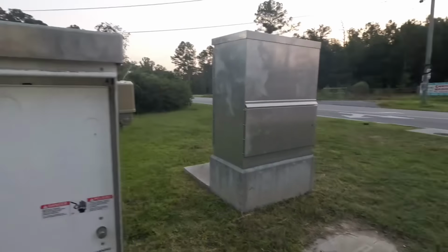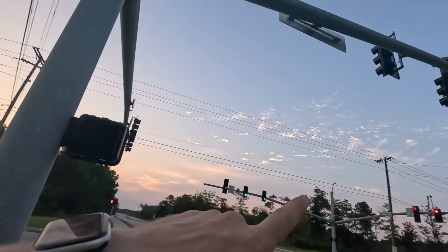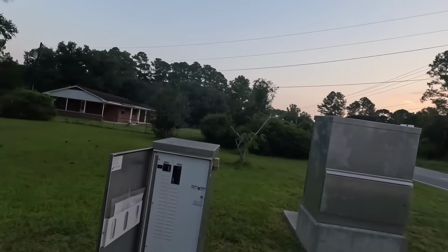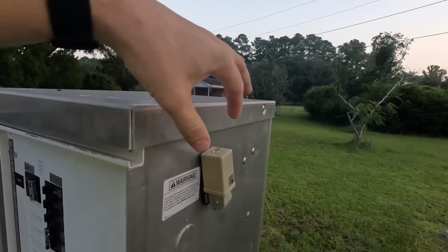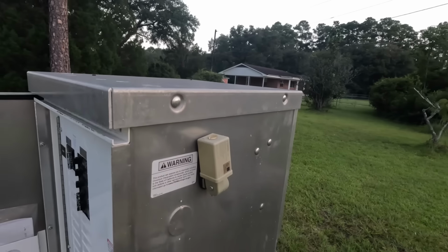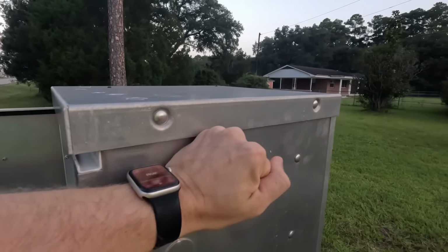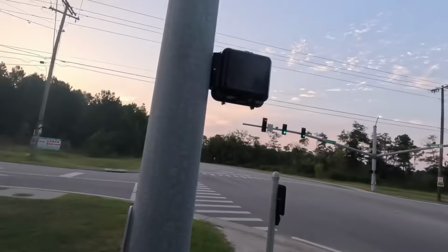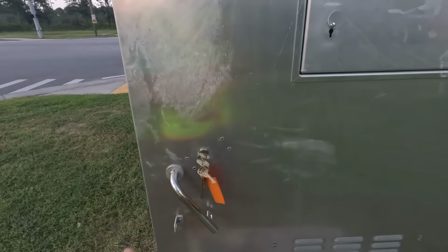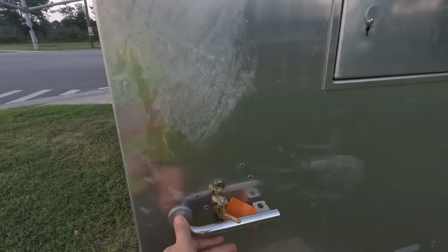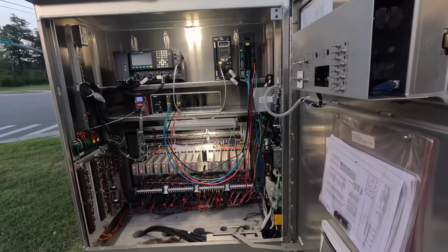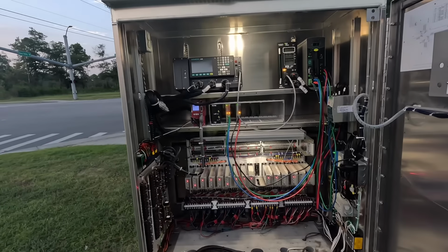The other breakers in here will feed power to the luminaire lights that are on the tops of each of these shafts. And that photo cell is what controls those luminaire lights. When this does not read enough light, if I cover it, you'll probably hear a contactor closing here, and you'll see out in the field that those luminaire lights have come on. So let's now open up this traffic signal controller cabinet here, and I'll show you some of the equipment that's used to keep you safe on your day-to-day commute.